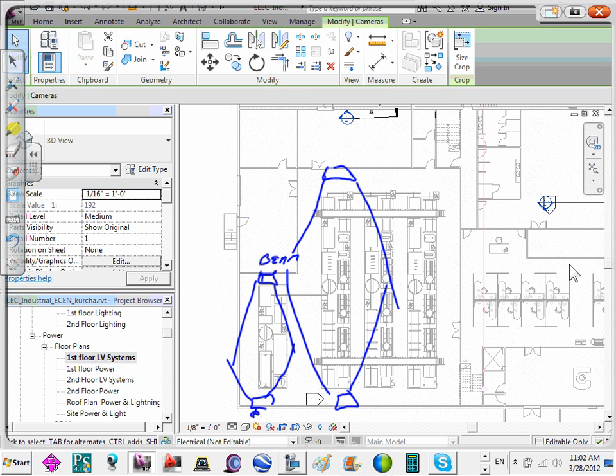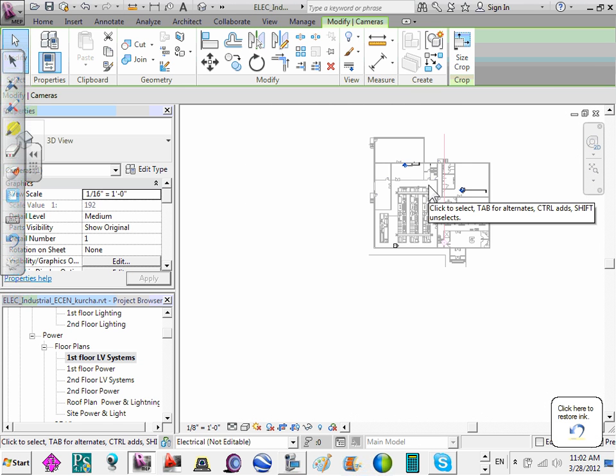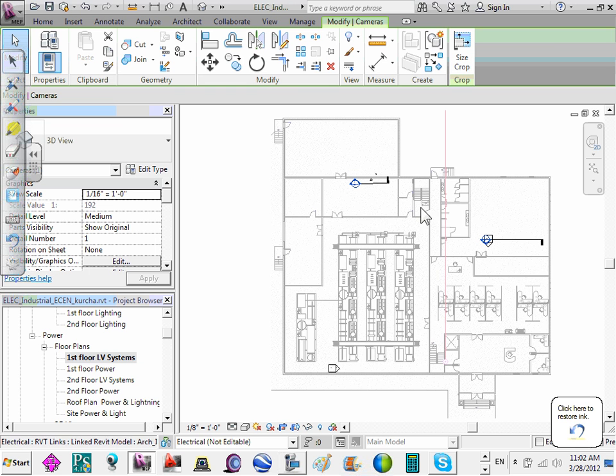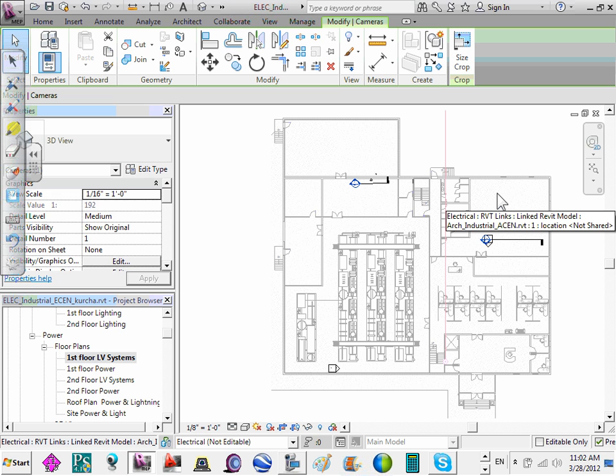So if you're coming into an existing building where there are existing notification devices, one of the things to look for is that you have to make sure that all the devices are synchronizable. NFPA code requires that if you have notification devices, they all have to sync at the same rate, because it can send people into shock, people who have, can't think of it right now. Seizures. Yeah. So it can send them into seizures due to the abnormal flashing, so everything has to be synchronized. So they flash at the same time, same rate, everything.